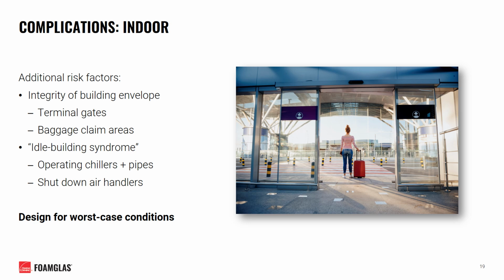Another risk factor is whether or not a given building will be subject to what's referred to as idle building syndrome. If a commercial building is designed to be unoccupied at times, they may choose to shut down the air handlers of the HVAC system. However, the chillers and chilled water pipes are often required to remain operational. This combination of unconditioned, high humidity ambient air along with the same chilled pipe surfaces can create a prime environment for condensation to occur. In any scenario, you'll want to consider your specific environment and always design around worst case conditions for your system.